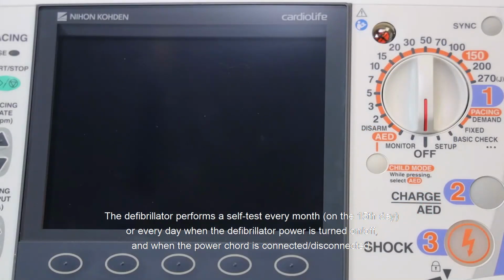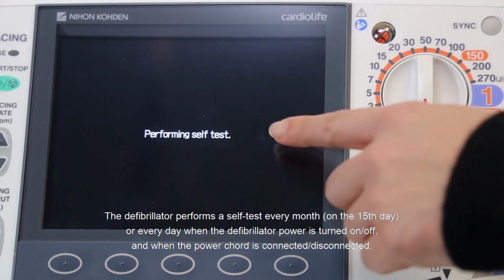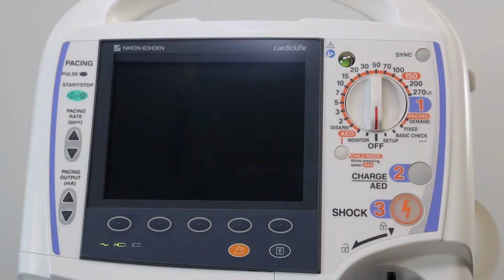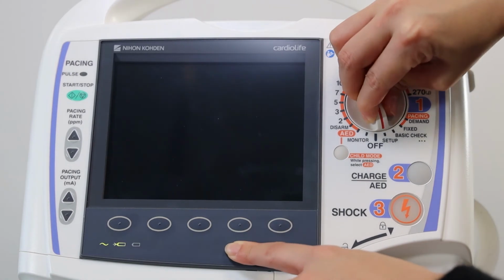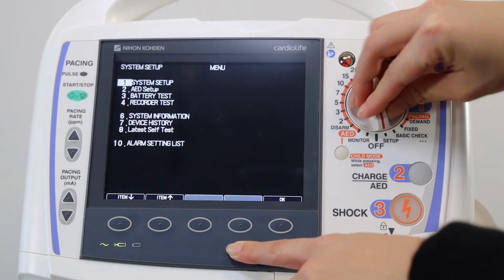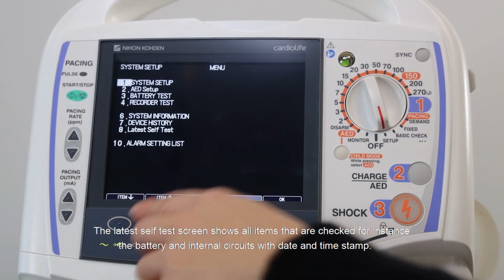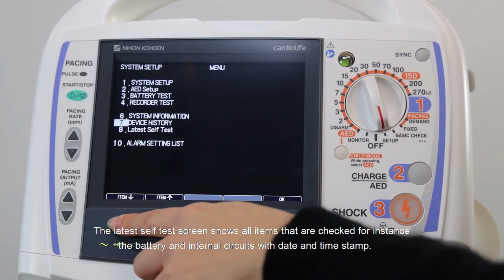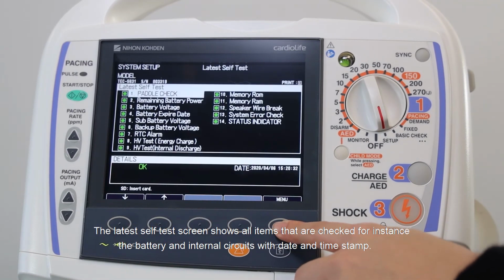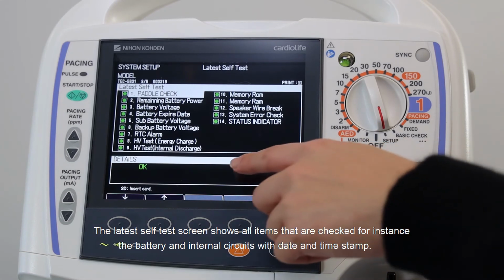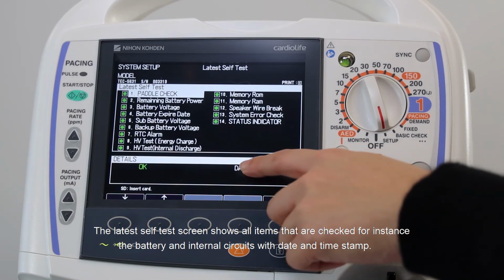The defibrillator performs a self-test every month on the 15th day, or every day when the defibrillator power is turned on/off, and when the power cord is disconnected. The latest self-test screen shows all items that are checked, for instance the battery and internal circuits, with date and timestamp.